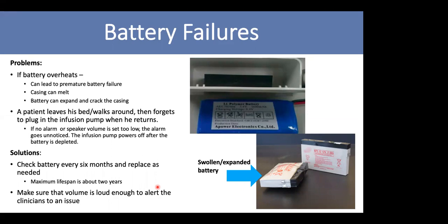And when the patient tries to move with the infusion pump, going to the washroom, anything, they're going to unplug, or someone is going to unplug and move, and they try to run on the battery, the battery is not working, it is going to fail. So that particular disaster is not good actually. So you have to be careful with that. Make sure to check the battery every time when you do the PM, all that.